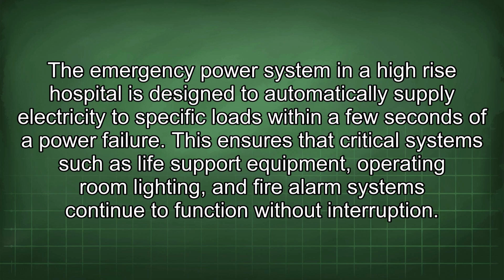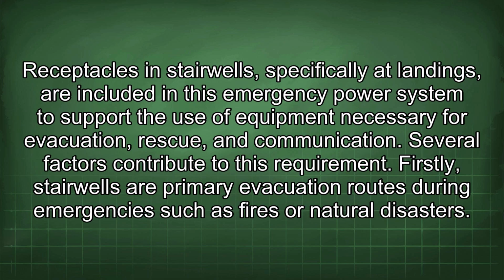This ensures that critical systems such as life support equipment, operating room lighting, and fire alarm systems continue to function without interruption. Receptacles in stairwells, specifically at landings, are included in this emergency power system to support the use of equipment necessary for evacuation, rescue, and communication. Several factors contribute to this requirement.